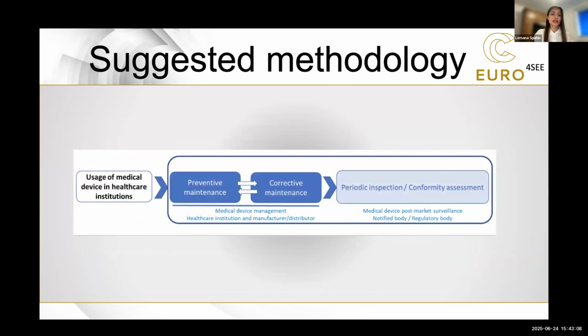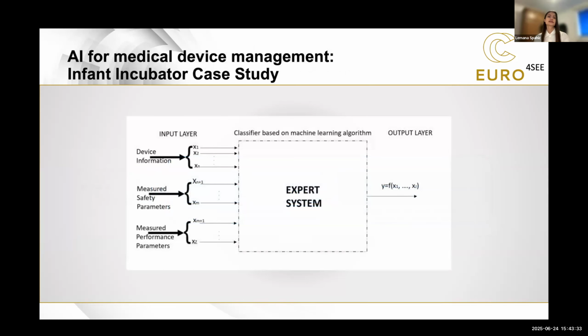Now, the suggested methodology, once the device is used in a healthcare institution, is to implement a framework that will allow for more preventive and less corrective maintenance, and to facilitate this through a combination of periodic conformity assessments and intelligent systems. Now, this is a brief overview of the infant incubator case study, and basically all the algorithms have the same gist. So we use the device information, which is related to the safety and performance parameters.